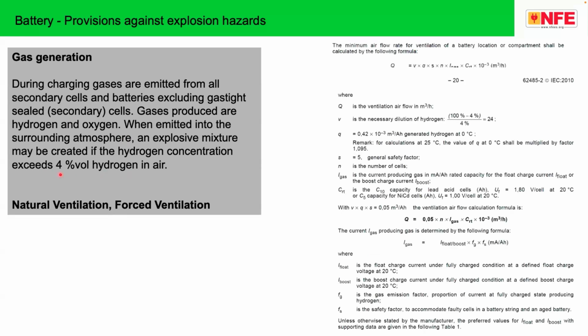The subject is very much engineered and included in the respective standard, depending upon the size of the battery, type of the room, type of ventilation. We can exactly calculate the ventilation requirements, and then the management can decide whether you need natural ventilation or forced ventilation. Please note, on the right side, you can see some calculation from IEC 62485 part 2. Here, this standard is providing the engineering solution for identifying a location where the battery is kept and what kind of ventilation is required.